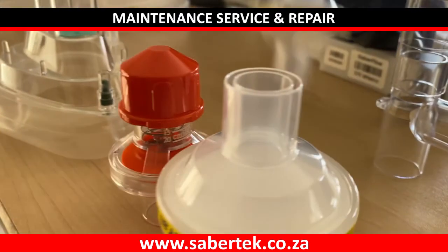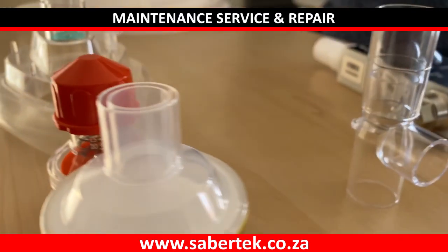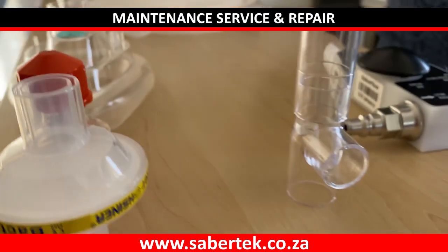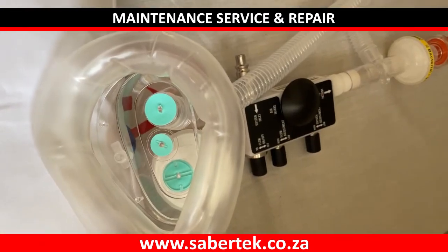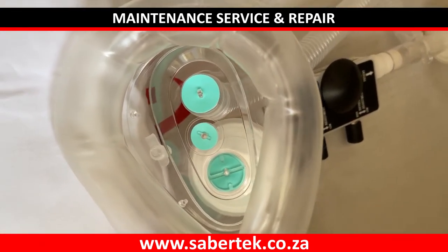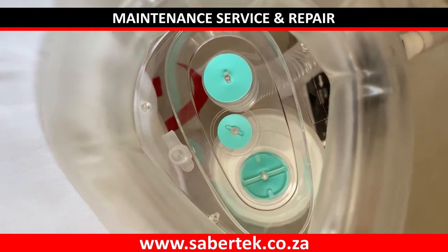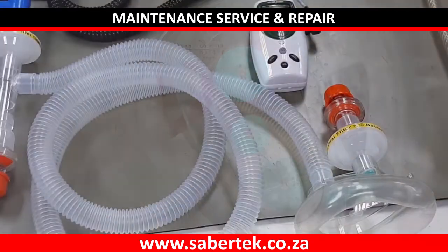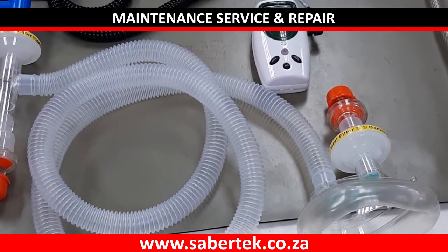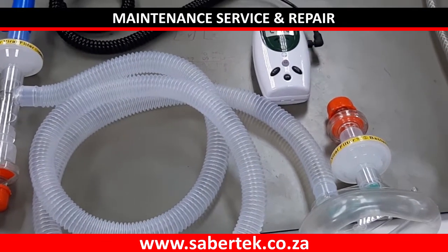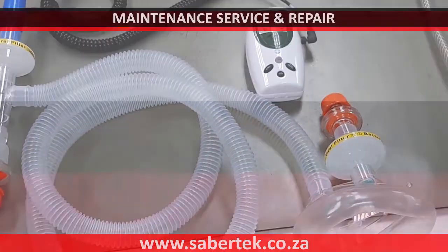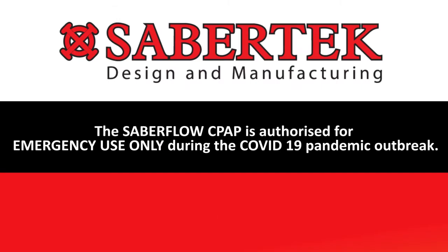The SaberFlow CPAP device does not require any routine maintenance or sterilization. Daily cleaning of the SaberFlow device is done by wiping down the device with a cloth soaked in diluted bleach. Alternatively, a 70% alcohol solution can be used. Full service and repair of the unit is available from the manufacturer. The SaberFlow CPAP is authorized for emergency use only during the COVID-19 pandemic outbreak.